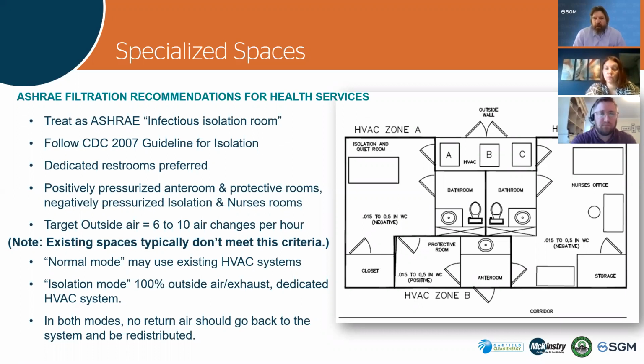Say in HVAC zone A, they can plastic off an area. If they don't have outside walls with doors, they may have outside walls with windows, and they can set up portable HVAC systems there, set up ones that will provide 100% outside air, heat and cool it, and then other ones that will provide the negative air and discharge all of it outside. So you're adding air in and discharging air out. You can still use supplies from the rooftop unit into the room for some of the air, but all of the returns have to be sealed off really well with plastic. You cannot have any of that return air going back to the main rooftop system and being redistributed through the entire hospital or school.